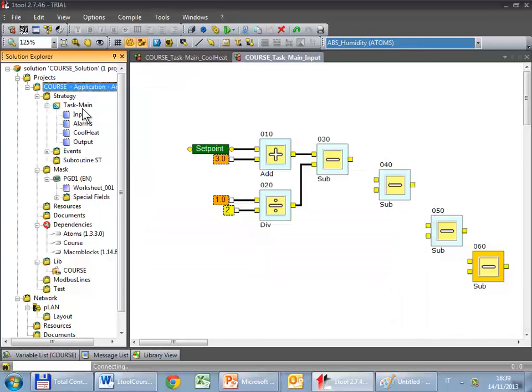The first part of the program reads the input and then manages the alarms, because alarms probably use the status of digital and analog inputs. After that, we manage the devices because they use the value of temperature as well as the alarms. After that, we define the status of the outputs because it uses status defined in these pages.